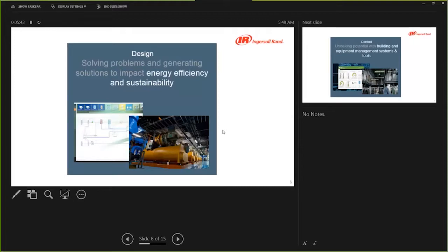Almost all poor air conditioning systems miss this critical step. And I would contend that perhaps 10% of the energy consumed for air conditioning in buildings is wasted because we didn't take this first critical step. We selected the wrong system, we guessed at equipment sizes, we guessed at building loads, we assumed that catalog information was accurate. That's not always the case.